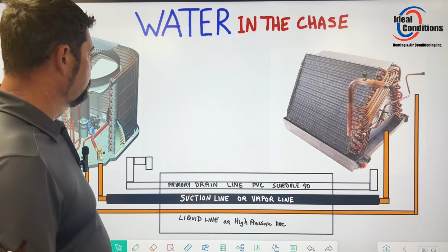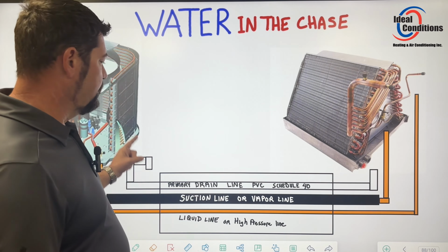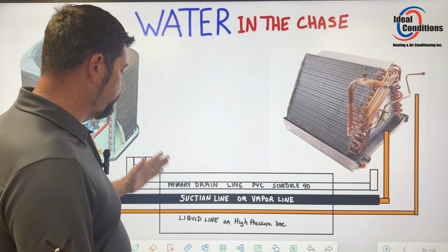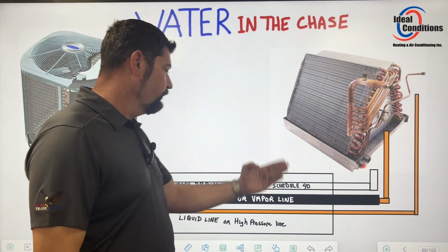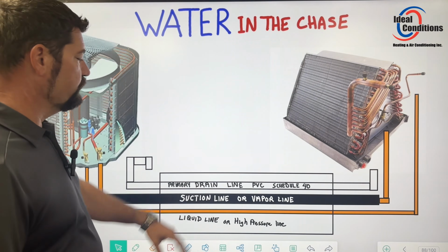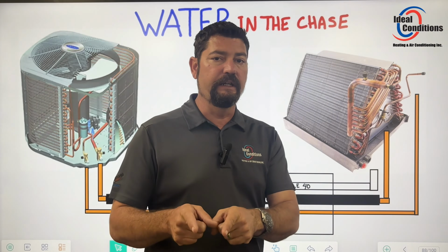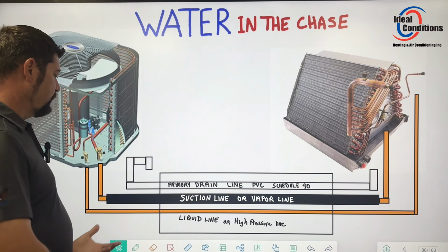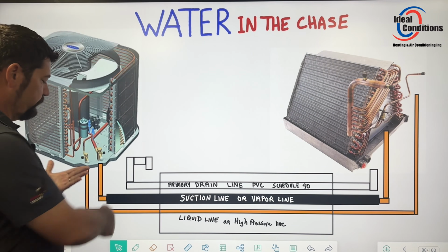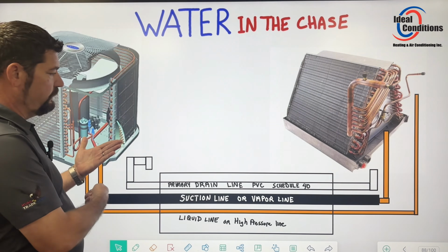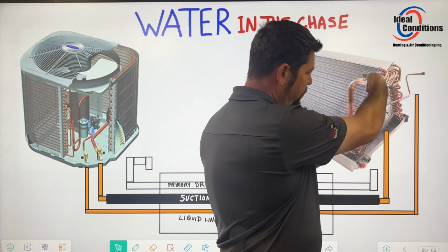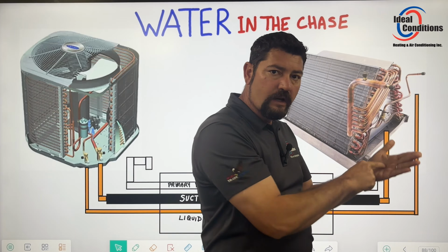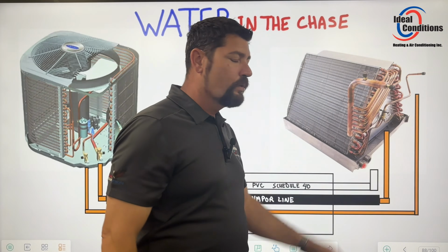So very important. You want to make sure that your drain line's always draining. If it's not, and it's not backing up, and your copper lines run through the chase, then I would say there's definitely water in the chase. If you wanted to prove that theory, very simply, you take your clamp off of whatever, plug it onto your meter. You can read the temperature here. Record the number right off the evaporator coil coming out of the cabinet, slide the Armaflex back, clamp it again, and read that number. There shouldn't be more than a degree or two.